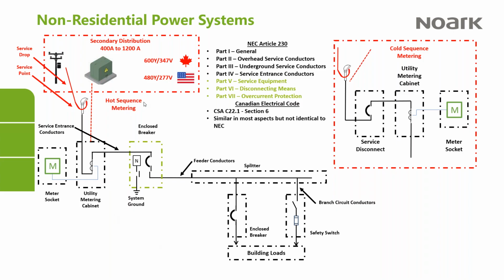So what I'm showing here is what's called a hot sequence metering system. The utilities typically specify what they want in terms of metering. So in hot sequence metering, the utility's power comes and joins onto these service entrance conductors. This can come in different forms, but in this example, which I tried to keep simple, the power flows through a utility metering cabinet, which only houses the utility's current transformers and in some cases potential transformers. The utility usually specifies the dimensions and the construction of that cabinet, and there are many manufacturers that make those cabinets. So that provides the utility with a place to meter the power.